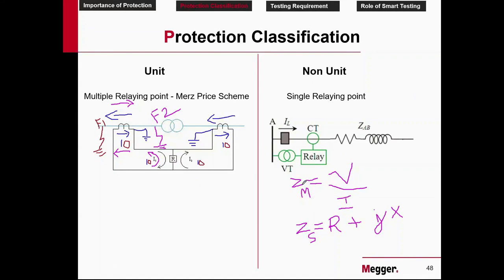So here what we do is, whenever your measured impedance is less than your set impedance, then it is a fault. If your measured impedance is greater than your set impedance, your system is said to be healthy. Okay, let's understand here. What happens when a fault occurs? Your voltage comes down and your current increases. So when your denominator increases, what happens to your Zm? Decreases. That's what we see here. During the time of fault, your Zm reduces than your set impedance.